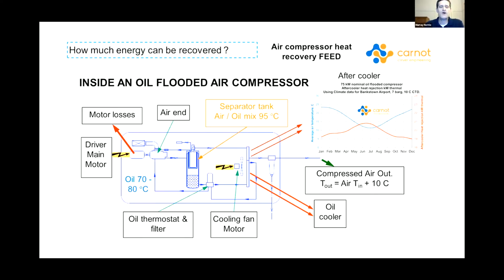The hot air-oil mixture goes into what's called the separator tank, and the oil drops out and the air goes out to the aftercooler. Now the whole mixture is kept at around 70 to 80 degrees, that oil going back in, and the resultant high separator temperature is kept up to 80 to 95 degrees. That is to stop water condensing in the system.